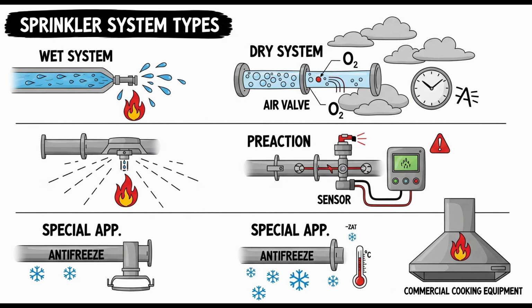Now let's really focus on the environment we mentioned right at the start, which presents perhaps the most unique challenges for water-based systems. Refrigerated spaces. This is where the ambient temperature is constantly below freezing. Yes, protecting areas maintained below 32 degrees F, commercial freezers, cold storage warehouses, is arguably one of the trickiest applications for water-based fire sprinkler systems. The constant primary risk is that any moisture or water that manages to get into the cold piping section will freeze solid and form an ice plug, completely blocking the pipe and rendering that part of the system useless in a fire. A frozen pipe is no pipe at all when you need water.